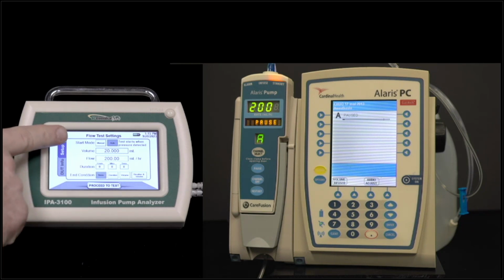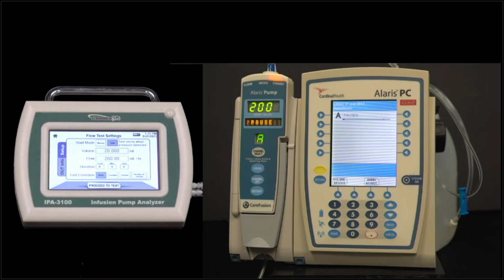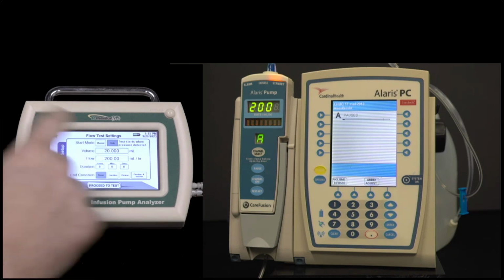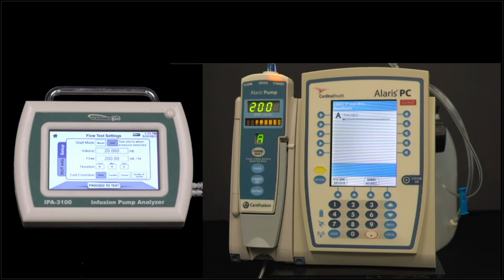Now, the other option that we have on the screen here is the start mode. So we've got manual or auto. Now, what that does is what we saw before. I started the test, and the unit just waited. It was ready to go. I don't have to worry about when I start the pump. So it will start measuring as soon as it sees the flow coming from the pump. The other mode, manual, it will automatically start measuring time as soon as I hit start. So then you have to synchronize the start of the test with pressing the start button on the pump.